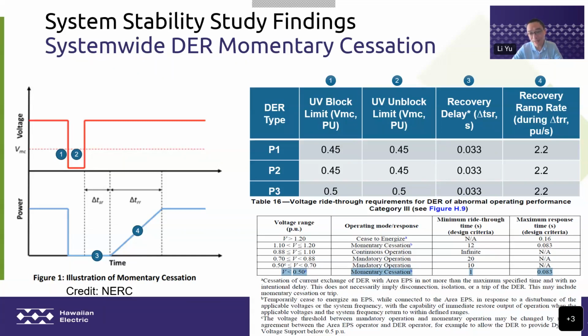We use the latest 1547-2018 standard as a base to estimate the DER momentary cessation recovery ramp rate, which is number 4 shown in this slide. We use that as the assumption for the ramp rate limit when DER recovers from momentary cessation, and we also use that standard to assume the recovery delay in the model. So we put all these parameters in our single-phase DER model, in our system-wide PSCAD simulation, and we see how DER momentary cessation affects our system stability. Next slide, please.